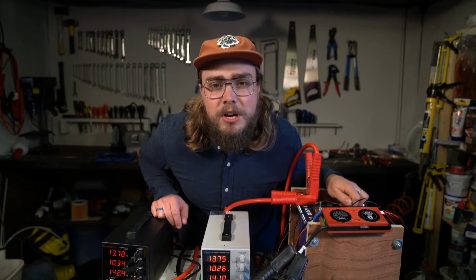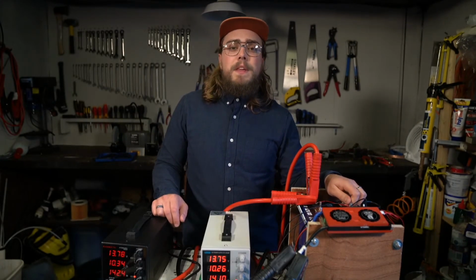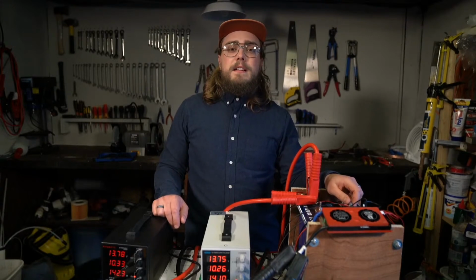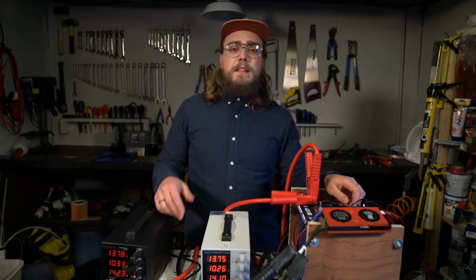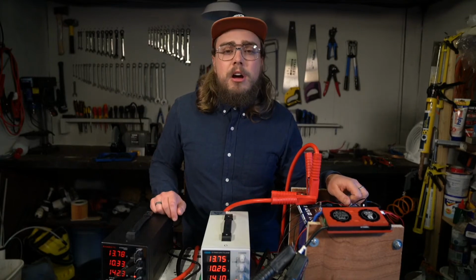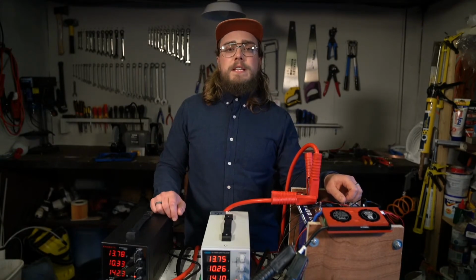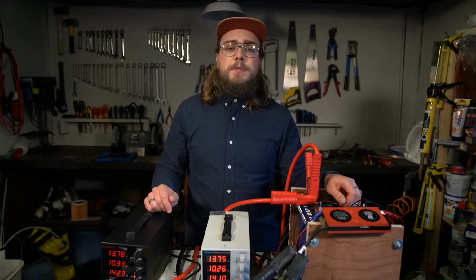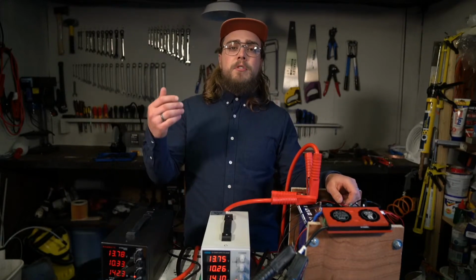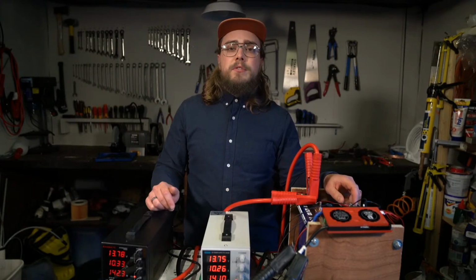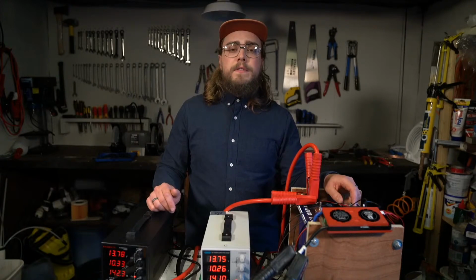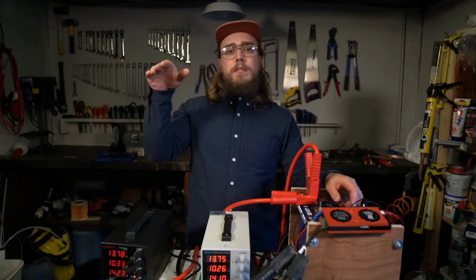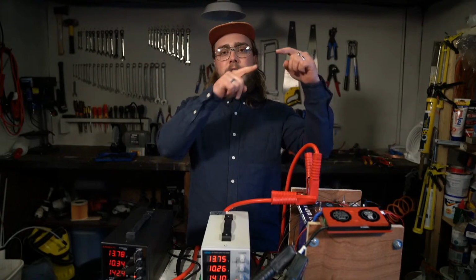Should I set my charger to only charge them to 95% maybe? Yeah, I think they will last slightly longer if you do that. If you set the threshold to stop charging at 95% and then put your low voltage disconnect to 15%, just work that out by checking the discharge curve of your battery.